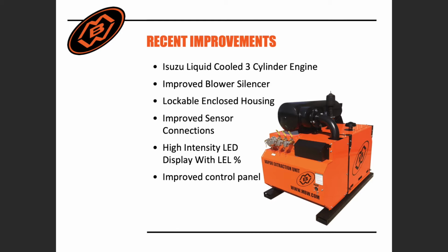There is a pump oil spot on the VEU control board. This pump oil spot is a great place to spray 4 to 5 spritzes of WD-40 onto the machine port to lubricate the blower for long-term storage or preventative maintenance while pulling a lot of water. This little step will help prevent the blower from rusting up over time if it is not done.